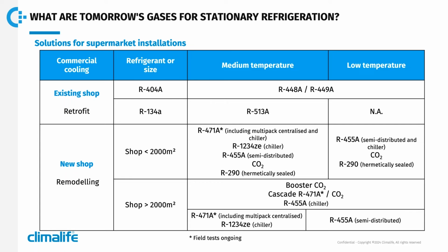For stores over 2,000 square meters, we have solutions that cover low and medium temperature, such as CO2 boosters, 417A or 515B and CO2 in cascade system, and 455A in chiller. We also have for medium temperature 471A in a centralized system, 1234ZE in chiller with an HTF in a secondary loop, and for low temperature 455A in condensing units. Each refrigerant provides a technical solution, but it is important to choose one that is easy to use, the safety associated with the refrigerant category in terms of flammability and pressures, the cost of installation and energy efficiency.